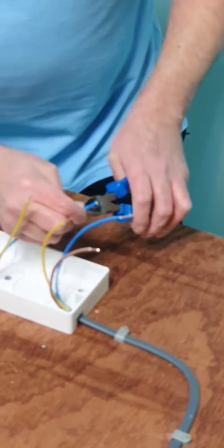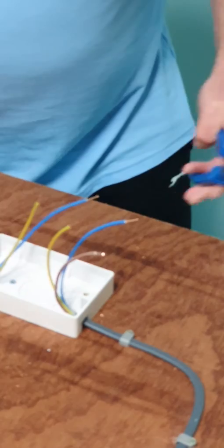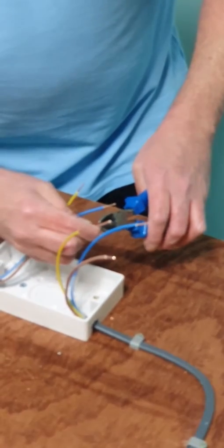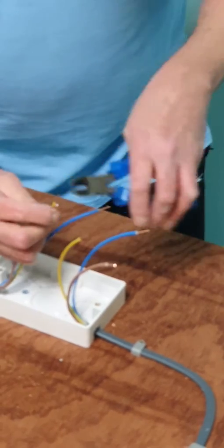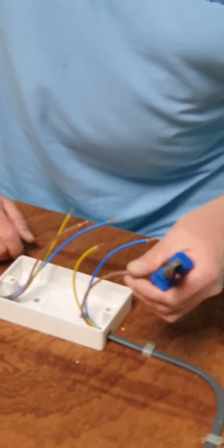Same the other side. Practice makes perfect. Again gentle squeeze. You don't want to be squeezing too hard because if we've got solid copper we damage that. When you're terminated into the socket you are likely to snap that off.